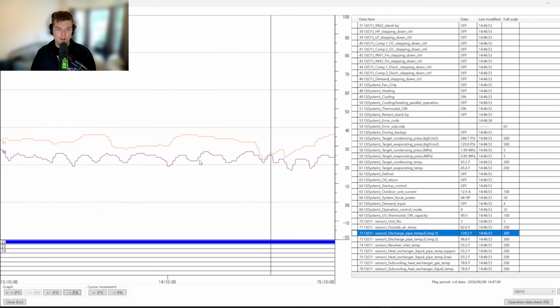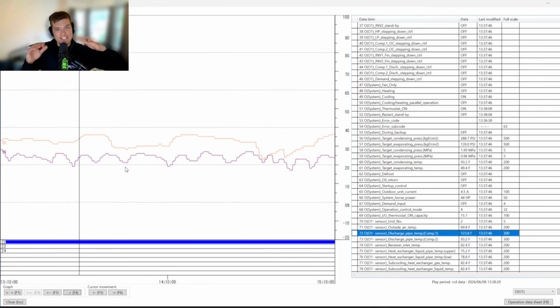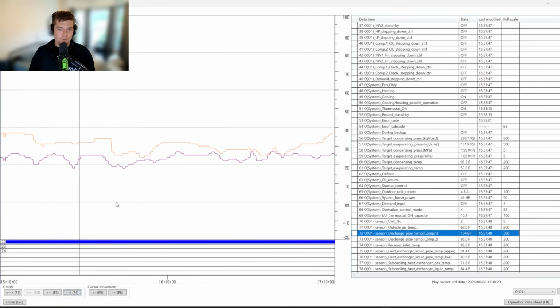We touched here. But you'll also find, with systems that have non-condensables in them, that the data on something like this mirrors the fluctuations, where they're always out of sync. One goes down, the other one's going up. But then as this one comes up, the other one's going down. I've seen that in a lot of data. I'm actually gonna make a video about that here soon. But those exact things all kind of play a part here.